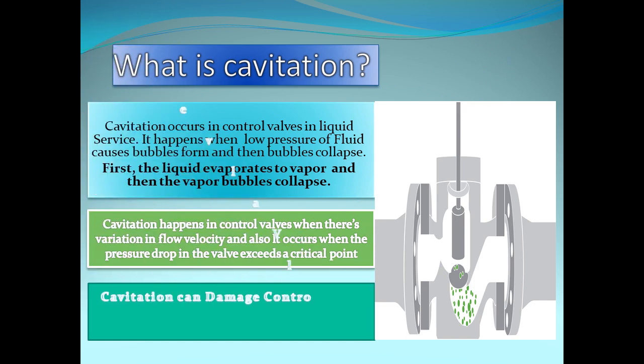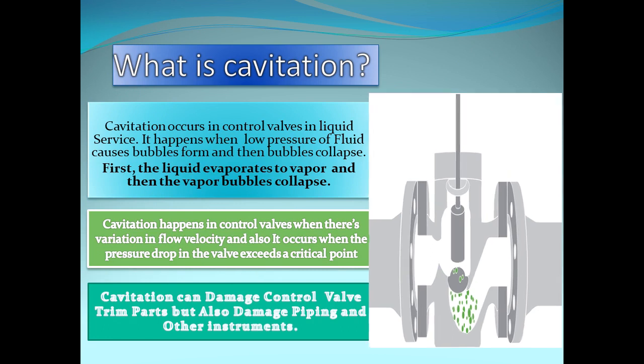What is Cavitation? Cavitation occurs in control valves in liquid service. It happens when low pressure of fluid causes bubbles to form and then bubbles collapse. First the liquid evaporates to vapor and then the vapor bubbles collapse. Cavitation happens in control valves when there are variations in flow velocity and also occurs when the pressure drop in the valve exceeds a critical point. Cavitation can damage control valve trim parts but also damage piping and other instruments.